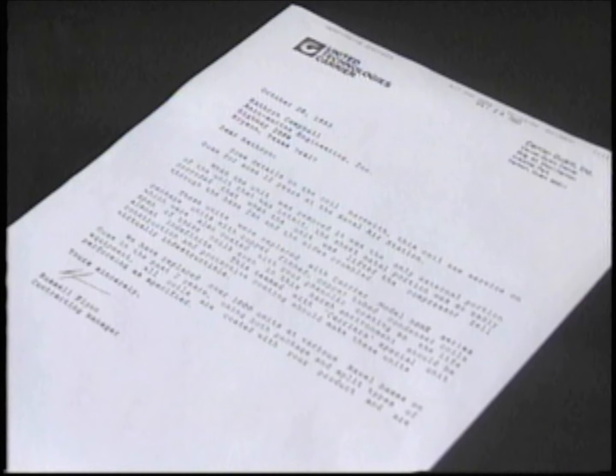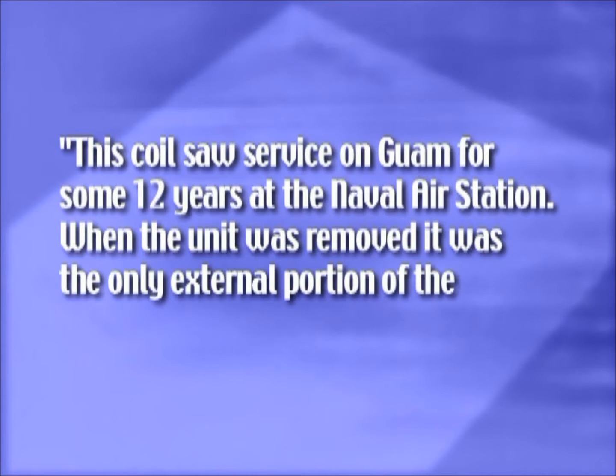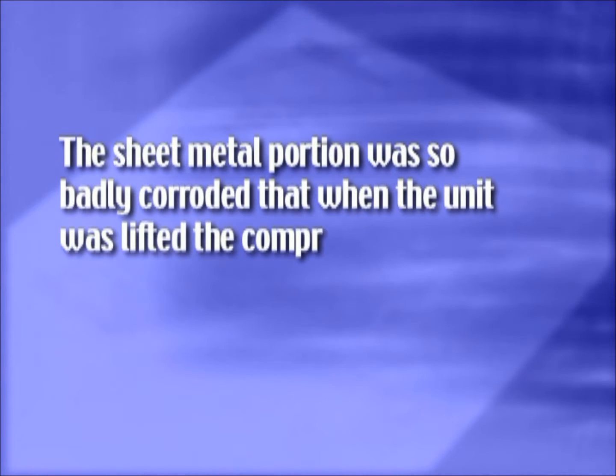Russell Flynn of United Technologies Carrier writes: 'This coil saw service on Guam for some 12 years at the Naval Air Station. When the unit was removed, it was the only external portion of the unit that was intact.